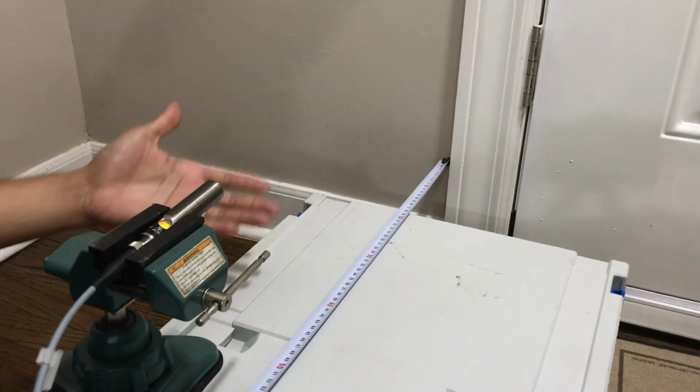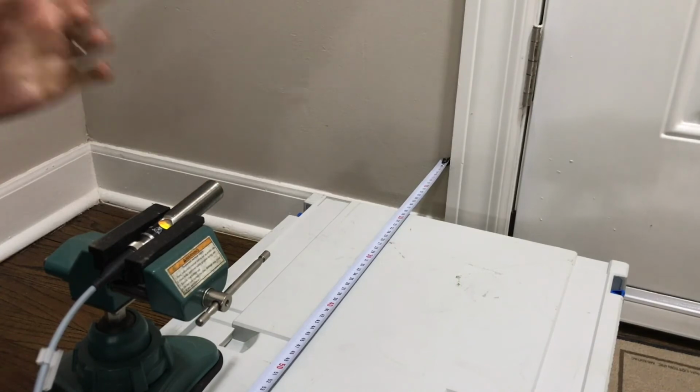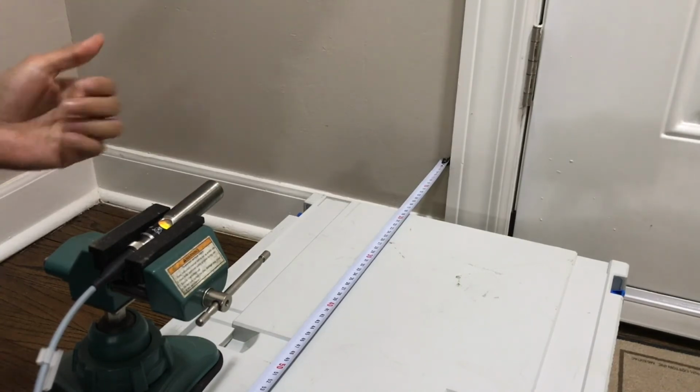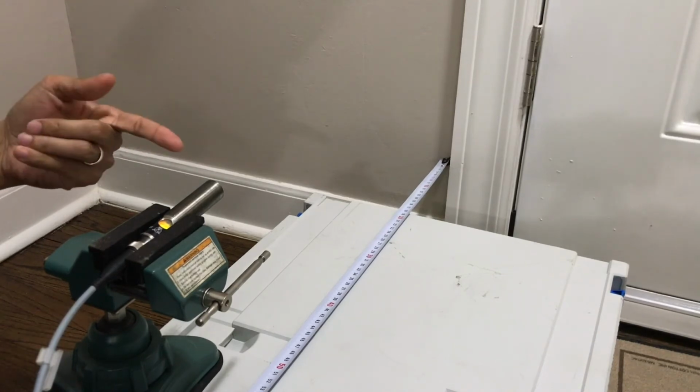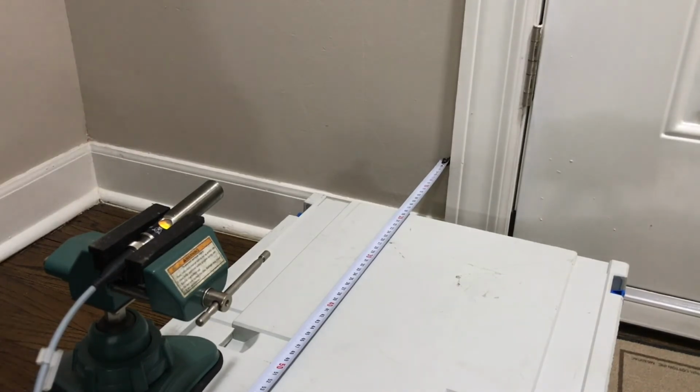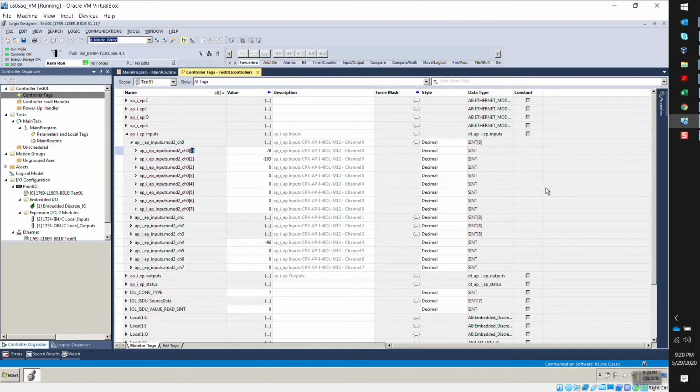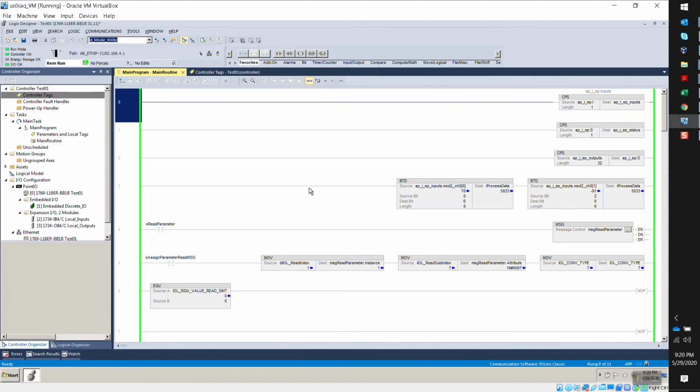So I should be seeing, it's in the process data, it's in 0.1 millimeters. So I should be seeing 5,000, right? A value of 5,000, and I'm not seeing that. I mean, if we look at the data right now, I can't make up 5,000 from these two values. So how do we fix this? The way to fix this is that we have to use these instructions over here. This is a bit field distribute. And what we use these instructions for is just to rearrange this data.